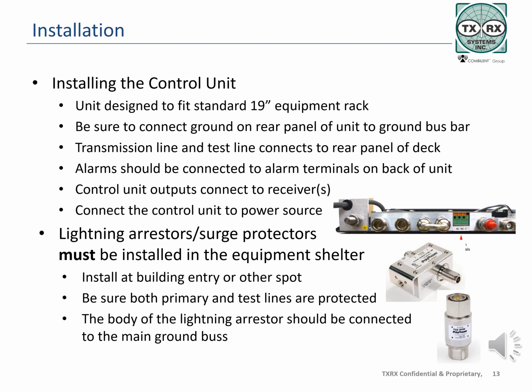Even if the system is not in a high lightning area, the absolute worst time to need protection and not have it is during a freak storm. Static discharge can occur at any time, so be sure to understand the requirements. All transmission lines must be surge protected at building entry sites. All feed lines must be protected. If the lightning arresters have a ground point on the body of the unit, be sure it is used.